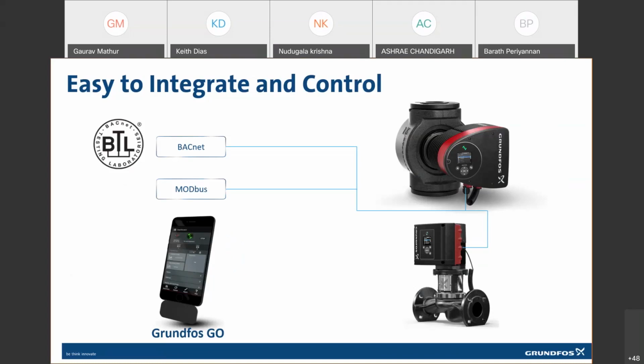Actionable insights can be obtained by digging into the data. With the help of communication, we are able to adapt these pumps based on changing outdoor conditions. I would like you to visualize for a moment that when you design a building, you have the total load of the building available with you. How about if you know what the load is in different areas at different timings, how much chilled water is going into different areas, and even the flow going into an individual AHU? That level of data can give you a lot of information which can convert into actionable insights, and all this is available in real time.